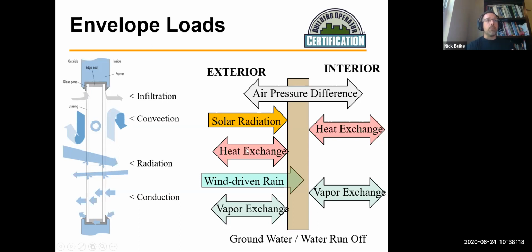I also like to talk about my other example with air pressure difference. Have you ever been to the Red Robin down there on Parker and Arapahoe Road, for my folks who live on this side of town, or any restaurant where you go up to that door and you're just trying to pull and pull and pull and you can't open that door? A lot of times that's because the building is super negative, and it's usually because the filters on the makeup air unit are totally loaded and the unit's not bringing in enough makeup air to replace the exhaust air that's being pulled out through the hoods. And so it makes the space go crazy negative. And so then you watch that person sit there and try to pull on that door a whole bunch.